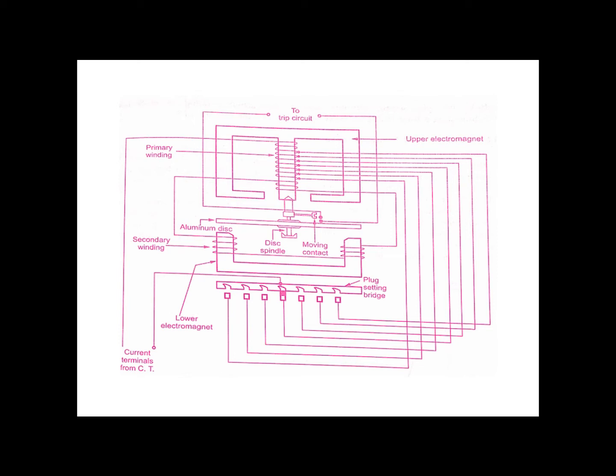With a 50 percent setting, the relay will start operating at 5 amperes. So the current setting is done with the help of the plug setting bridge (PSB).